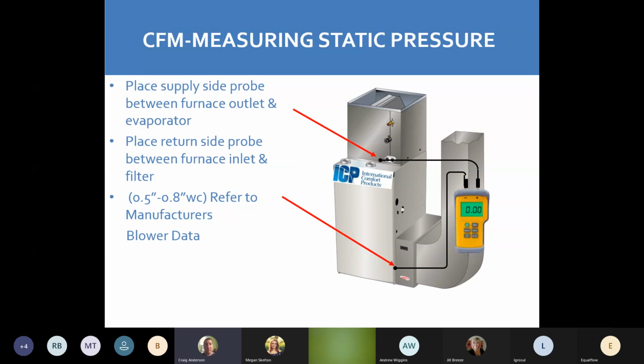Static pressures. If you're not checking your static pressures, start checking your static pressures. We're dealing with the ECM blower motors. They're looking to operate within a certain static pressure. If they're not, they're going to overheat and shut off. They're going to give you nuisance high limit calls. They're going to give you nuisance freezing of this unit.